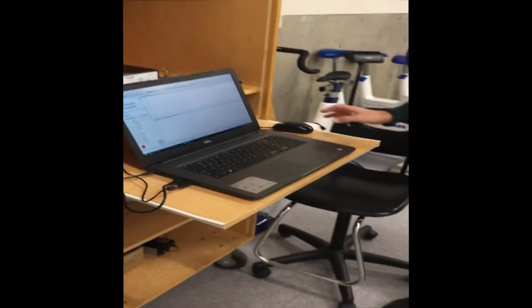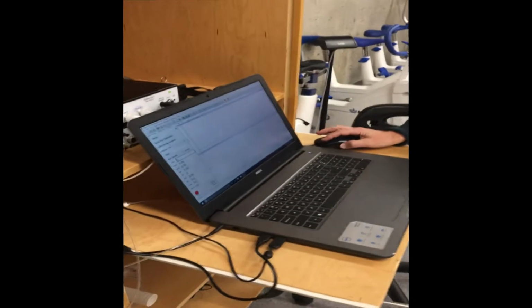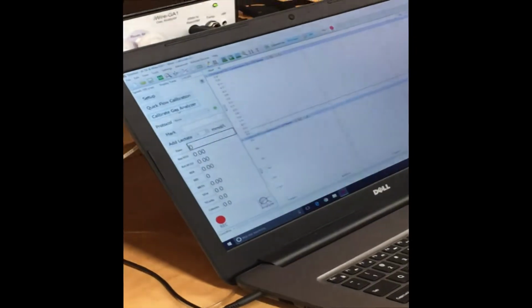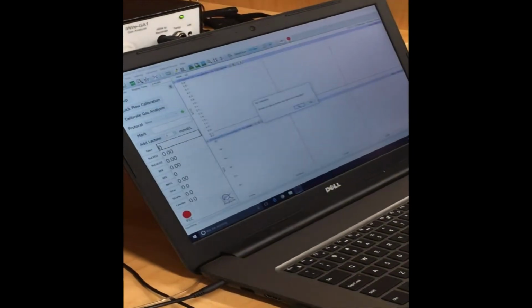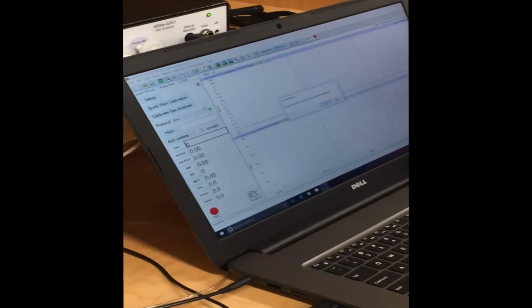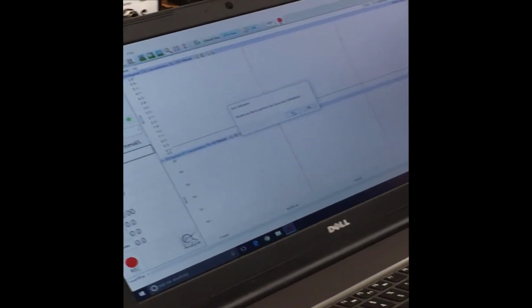So the very first thing that you need to do to calibrate it is simply click on the Calibrate Gas Analyzer button. So we click on the Calibrate Gas Analyzer button. It says, would you like to do a calibration? We say yes.